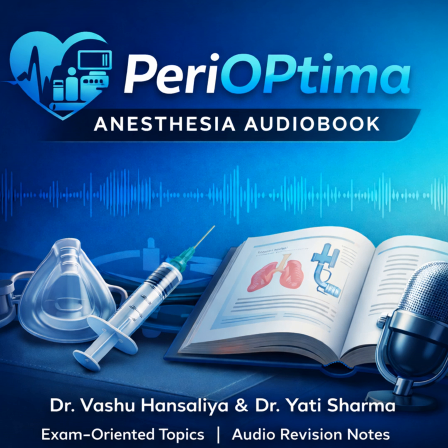Why disconnect the hose? You've already opened the cylinder. Isn't that enough? No, because you don't know why the pipeline failed. It could be low pressure, yes, but it could also be contamination. Or the pressure might just be fluctuating. If the pipeline pressure flickers back up above 45 psi for a second, the machine might try to draw from that bad pipeline again because of that pressure gradient we discussed. By disconnecting, you physically isolate your machine and guarantee you are running purely on your clean, known cylinder supply.